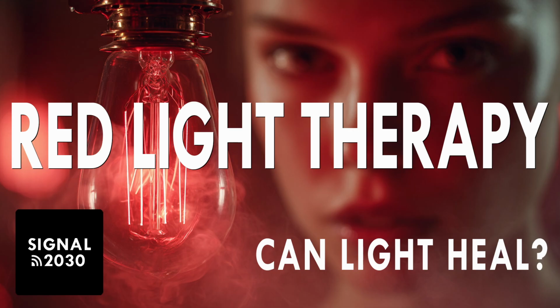But be a bit wary if a device lists tons of slightly different NIR wavelengths. It might just dilute the power at the most effective wavelengths. Focus on those core ranges. Okay. Next up, power density or irradiance. You said this was critical. Absolutely critical. Higher irradiance means you can achieve the target dose in a shorter time. But here's the huge catch.